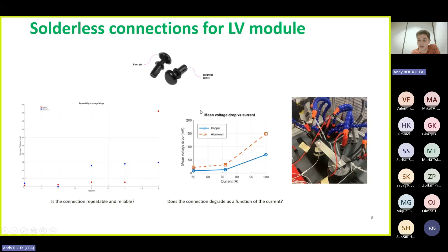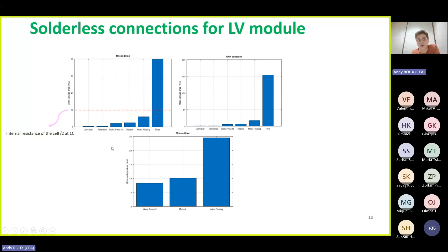Finally, this graph compares all the solutions with our threshold of 20 millivolts. What we see is that all solutions are below the threshold, except the rivet one, for the reason explained in the previous slide. But we have all the values of the voltage drop for each connection at different amperages, which is useful for choosing which connection we're going to use inside the module.